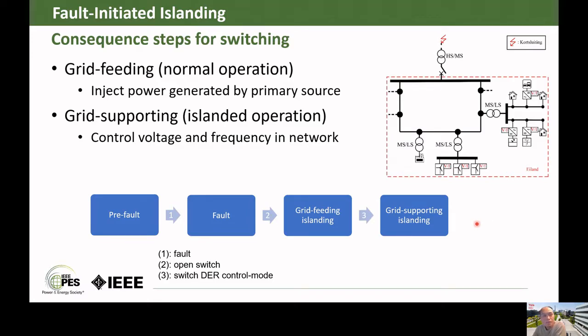In this switching possibility, it is very important to determine the operations of the DER inverters associated with it. The 2 main operation schemes for DERs in this switching sequence are grid feeding, considered the normal operation of the DERs before a fault occurs, and grid supporting mode, which is when the isolated operation mode is activated.